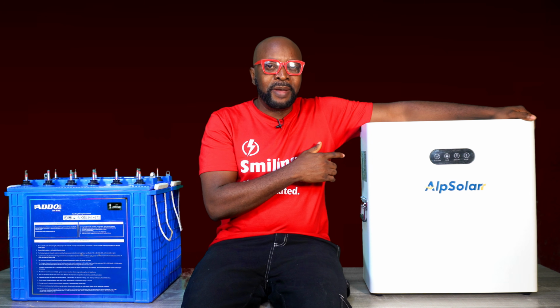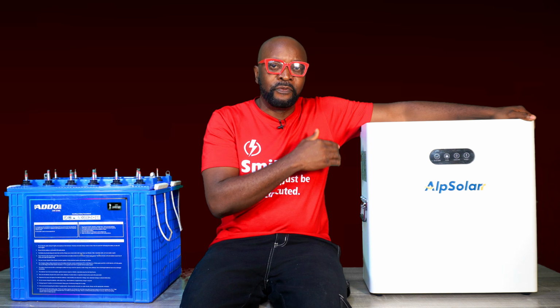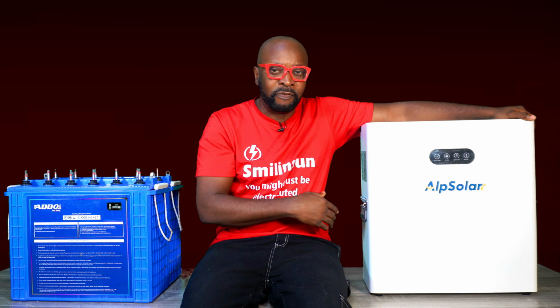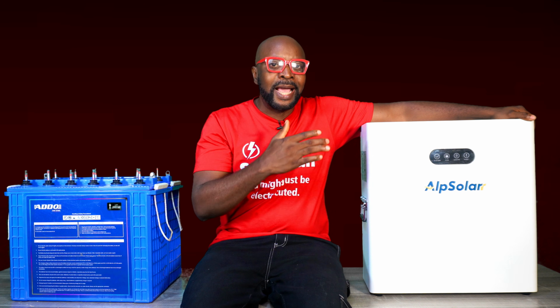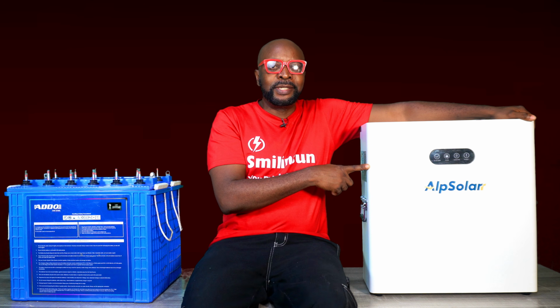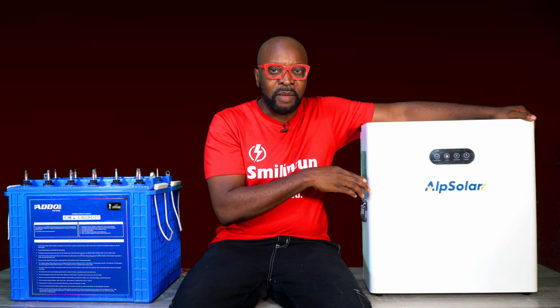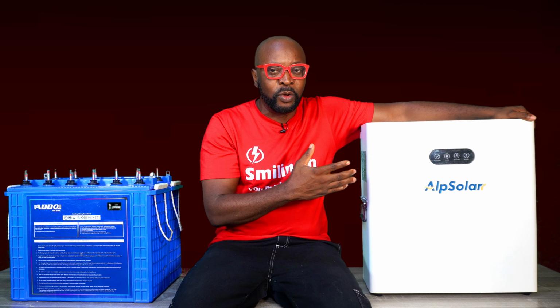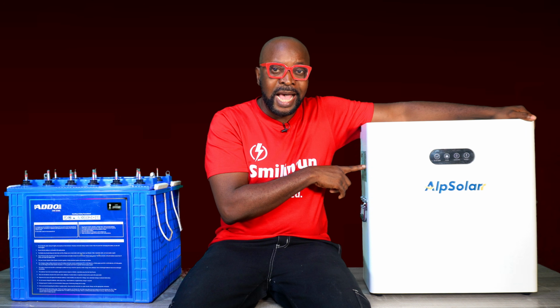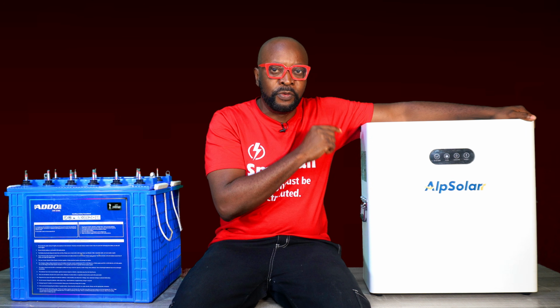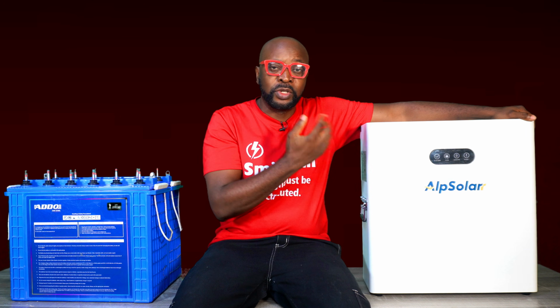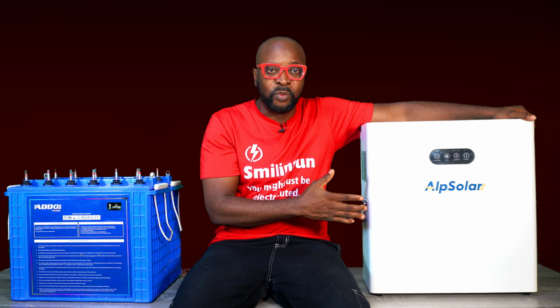The lithium battery has a charge voltage range from 56 volts to around 58.4 volts. Anything higher than that, the battery management system is going to kick in and shut down the system real quick, because it's seeing an excessive voltage which it deems very harmful to the cells of the battery.